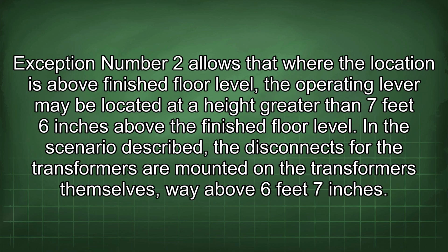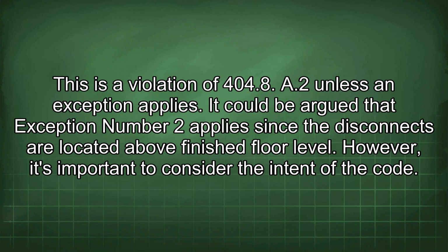Exception number 2 allows that where the location is above finished floor level, the operating lever may be located at a height greater than 7 feet 6 inches above the finished floor level. In the scenario described, the disconnects for the transformers are mounted on the transformers themselves, way above 6 feet 7 inches. This is a violation of 404.8 A2 unless an exception applies. It could be argued that exception number 2 applies since the disconnects are located above finished floor level.